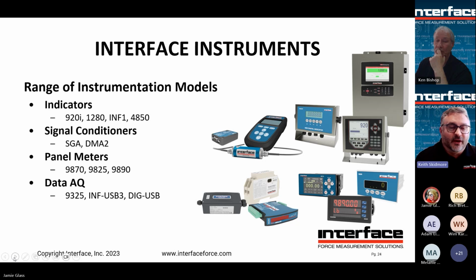Here are some examples. Indicators have a display on them. They can be self-contained, can have lots of fancy functions for controlling, relays and things. You can have alarm points. They can have special programming, say, to monitor the angle of a crane boom so that the maximum capacity may vary with the boom angle. They could be calculated and alarmed or displayed. Signal conditioners take the sensor signal and convert it to something else like 4 to 20 milliamps or a digital Ethernet, EtherCAT, Profinet, whatever, to attach to, say, an existing network.